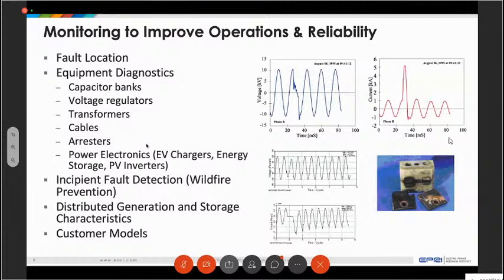That characteristic means that as the voltage regulator was going from one tap to another, it actually interrupted the current and then reinitiated the current very, very quickly. And that was happening over and over again, and arcing was occurring during those interruptions. Because of the power quality monitoring, they were able to find this problem before it caused the whole transformer to fail. So it was very important, and the value of the monitoring was paid for by saving that one transformer.